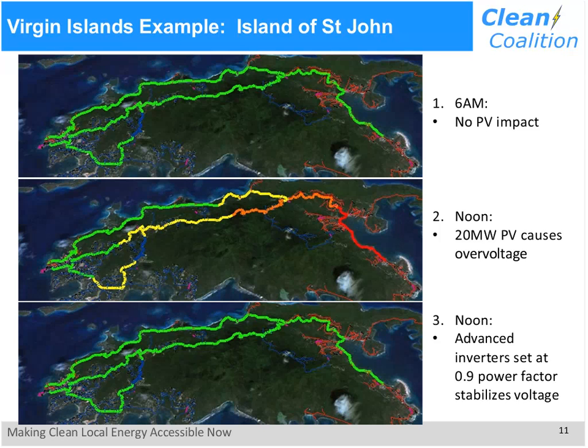But at high noon, if you haven't done anything other than deploy the solar with a unity power factor setting, meaning it's just pumping out 100% kilowatt hours, you have a situation where the ends of your feeders are actually offline, out of the allowed voltage boundaries. Other parts of the feeders, closer to the substation, are close to going offline too.